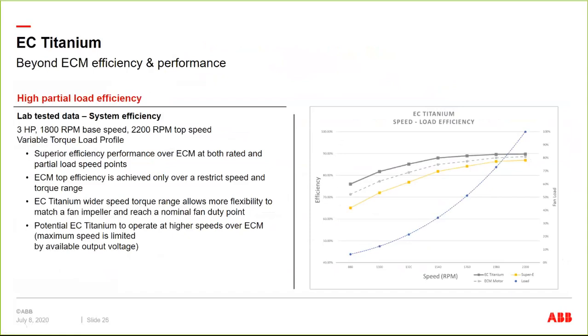And then do your calculations and say, how much energy am I actually saving for my end customer when operating at those points? Because if I did the calculation up here at full load and full speed, that nominal percentage difference doesn't really give you a whole lot in your payback analysis. But the key to this technology is that as I come down in the speed load point, we are maintaining our efficiency much higher than an energy efficient motor, induction motor, or traditional EC motor, which is this dash line. And in our testing in the lab, it's as much as a 16% differential between induction and can be up to 10% higher than a standard EC motor at partial load speed points.